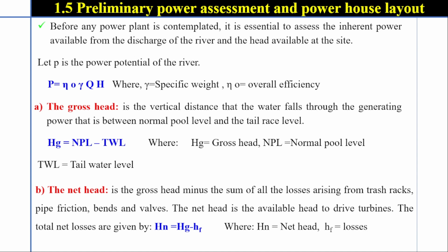Gross head is calculated by using this formula: gross head is equal to normal pool level minus tailwater level. Net head is the gross head minus the sum of all the losses arising from trash racks, pipe friction, bends, and valves. The net head is the available head to drive turbines. The total net losses are given by net head is equal to gross head minus head due to friction loss.